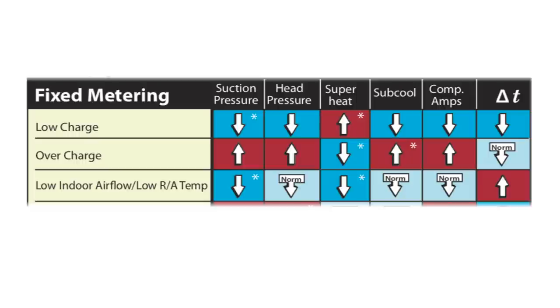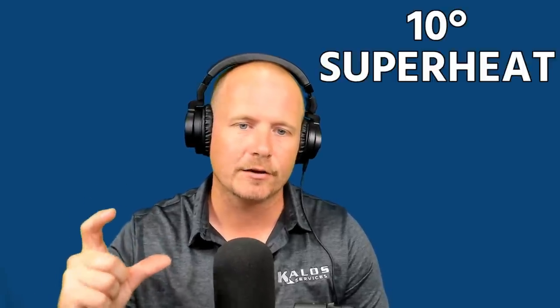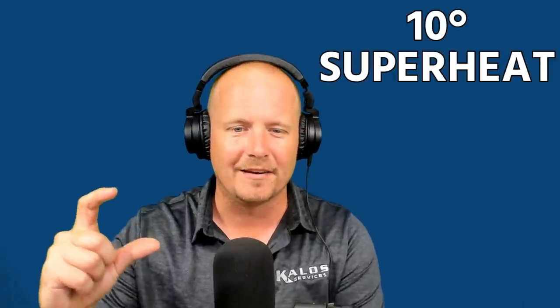Now let's look at the difference between system types. On a fixed metering device, when you have low airflow you're going to have low superheat and low suction pressure. On a TXV system, you are not necessarily going to have low superheat. It does tend to creep down a little bit — it's really more normal to low. So if you're used to seeing 10 degrees superheat on a system, with low airflow it may be down to around 8. The TXV's job is to maintain superheat, so it won't go to zero.